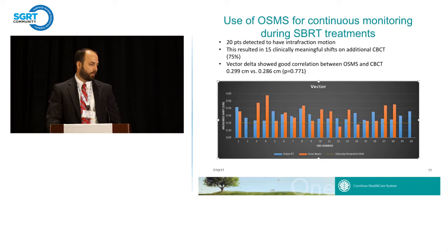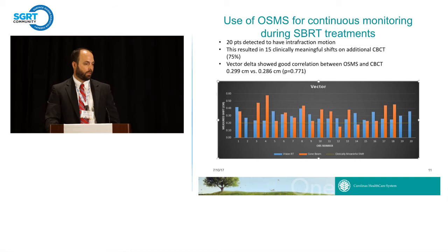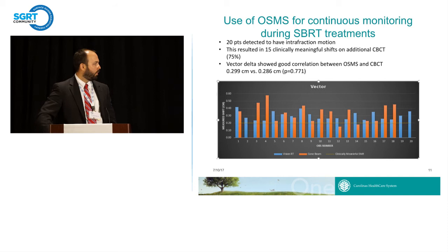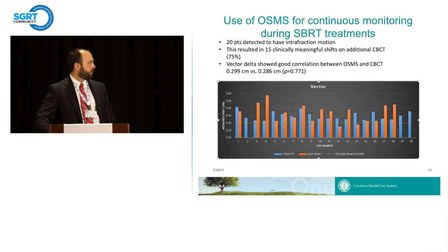We're still acquiring this data, but our initial results will be presented later this year. We've had 20 instances of intrafraction motion detected by OSMS, resulting in 15 clinically meaningful shifts on additional cone beam CT — so about 75% of the time when we detect something on OSMS it leads to a clinically meaningful shift. We also saw very good correlation between the projected shift from OSMS and the actual shift on cone beam CT, right around three millimeters on average. The blue bars show the suggested OSMS shift and the orange bars show the actual shift performed based on cone beam CT, and most of those correlate very nicely.